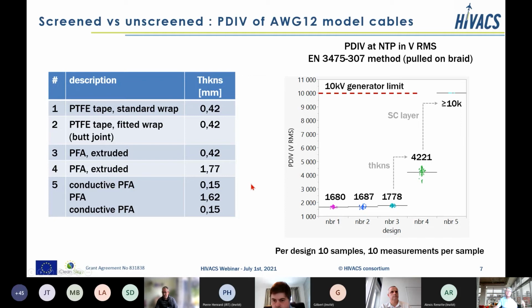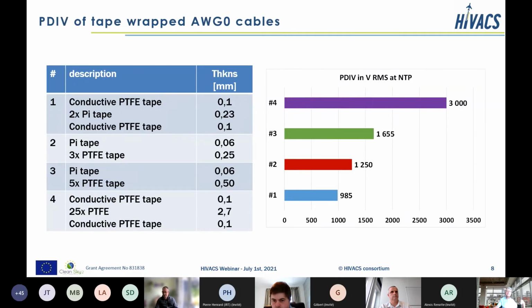In the next step, we also tested bigger size cables using a gauge 0 conductor. And here we have two screen cables, the number 1 and the number 4, where we have been using conductive PTFE tapes as conductor screen and insulation screen. And the design number 2 and 3 is, let's say, a standard design using an insulation with a Pi tape on the conductor and PTFE tapes above that. And we made, of course, different thicknesses, so 0.25 and 0.5 millimeter.